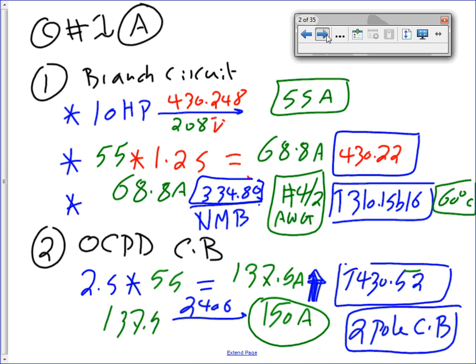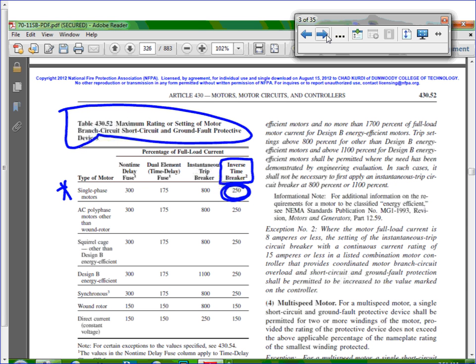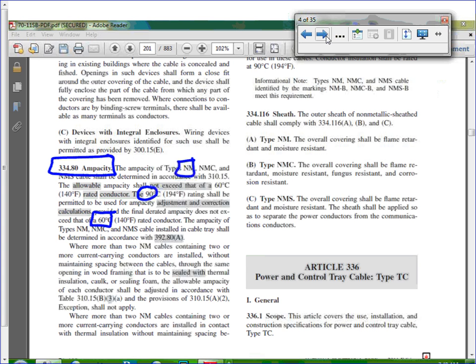The 2.5 is coming directly from right here. You go to this table that you guys highlighted, single phase, 2.5. And to answer my friend Adam, why did I go to the 60-degree column? If you go to 334.80, it will tell you you have to use the 60-degree column for sizing, but 90-degree only for derating. So don't get confused. This is derating. This is sizing. And you guys remember how we distinguish clearly between derating and sizing.